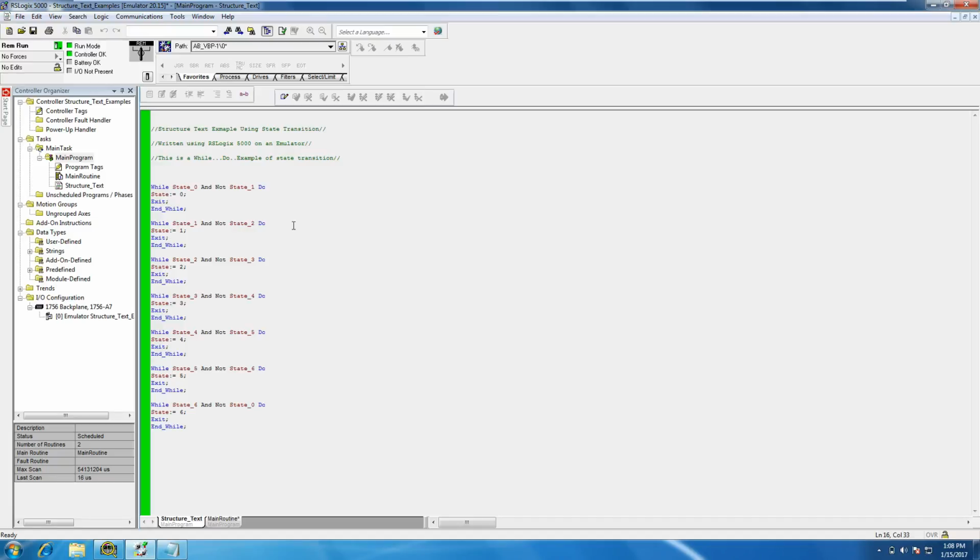We don't always look at our programs all the time, so we don't always have them open. So if the fault had occurred, you could come back and it would trap the fault code, and even if somebody reset it in the middle of the night to get it back running, you could detect exactly what happened just by looking back at the fault code, and you would know exactly where in the logic you might have a problem, and you could fix it.